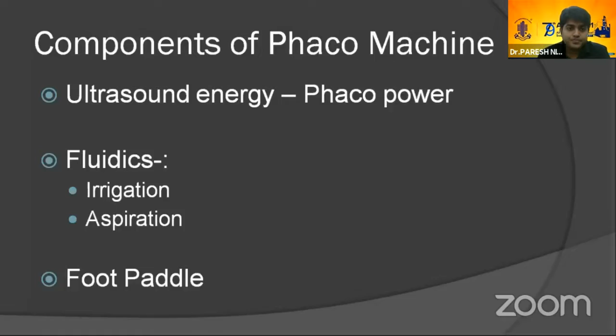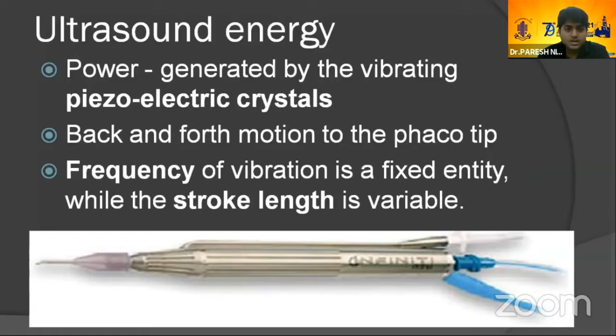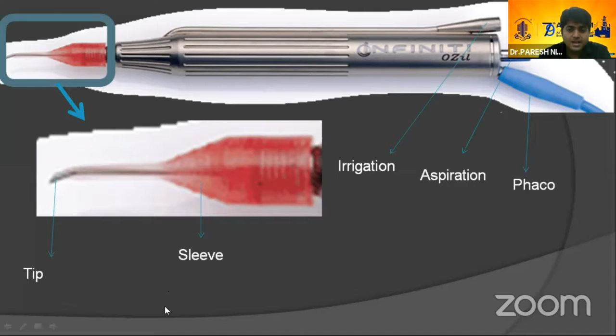If we talk about the ultrasound probe, it gets its energy from the vibrating piezoelectric crystal, which moves the phaco tip back and forth, creating a jackhammer effect. The frequency of each individual handpiece is fixed depending on the company and the phaco handpiece, while the stroke length can be variable depending on the settings which we set. Among the components, we have one irrigation port, one aspiration port, one port for delivering the phaco energy, and the tip is covered by the sleeves. We have different tip sizes and sleeve sizes.